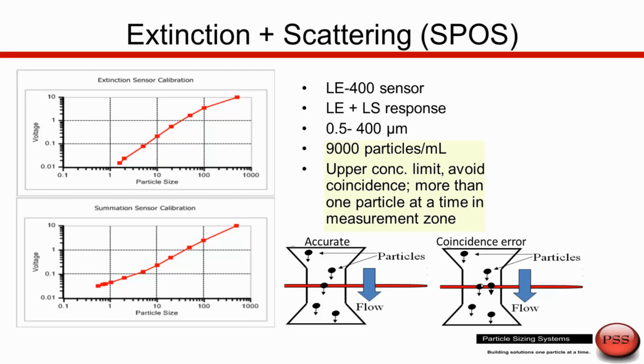But if we have more than one particle at a time passing through the sensing zone, then we would take these two particles and count and size them as one larger particle. That leads to what we call a coincidence error. In order to eliminate or at least minimize the coincidence error, we need to be aware of the concentration going through the sensor. There's a concentration limit for the sensor of 9,000 particles per ml. If we exceed 9,000 particles per ml, then there may be a coincidence error associated with the result, and we want to avoid that. So it's another physical aspect of the sensor specification we need to be aware of, and this may affect how we prepare the sample prior to measurement.